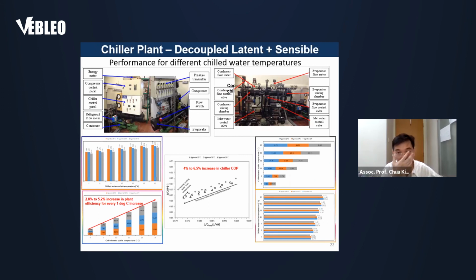For example, I need to highlight that if you can remove the moisture from the air for big systems, you can remove the moisture from the air at the air handling unit. In other words, the chill water that you previously provided to your air handling unit needed to be about 5 to 6 degrees. Now you no longer need to operate at 5 to 6 degrees. You can provide chill water at a much higher temperature, 15 to 18, or even 20 degrees, rather than 5 to 6 degrees, because the chill water no longer needs to condense the moisture from the air. The chill water simply needs to cool the air to a comfortable level.